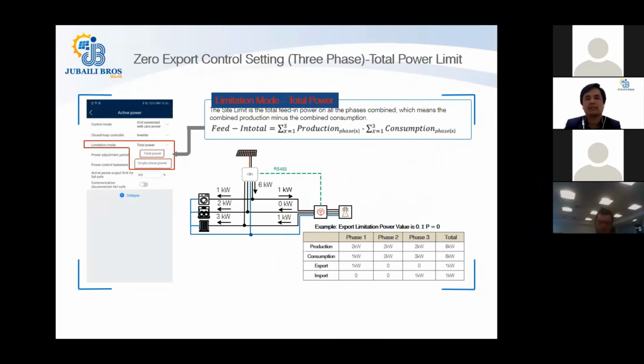Zero export control setting with the total power limit. Now you have a three-phase PV system, and you are doing a zero export control. In this scenario, you have the total power option, or you have the option of the single phase power. In the single phase power option, for the phase that has the maximum power, the meter or the system will not allow any excess generation going toward the grid side on that phase. It will be explained in the next slide, but this slide is specifically about the total power limit option.